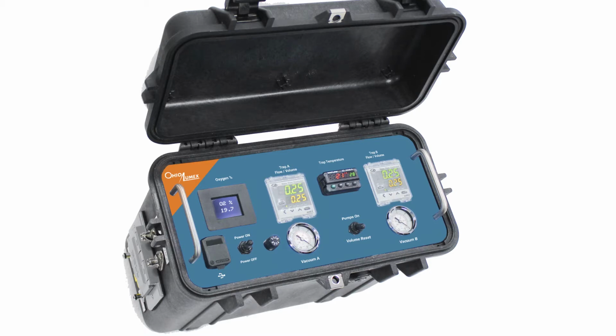Since there are 2 sampling trains, the console contains 2 pumps and 2 mass flow controllers. The console also includes an oxygen sensor if that option is selected upon purchase, as well as individual vacuum gauges for each sample train and a Watlow temperature controller that can be used to regulate the 750-watt probe heater.